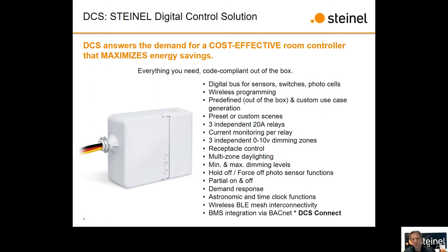One of the strongest differentiators in the DCS is the 3 independent 20 amp relays, where all the other guys in the market give you one 20 amp relay divided across 3 channels. Why is this so important? Well, our DCS can allow you to have both 277 volt and 120 volt circuits on the same controller. So if your plug load is running at 120, but you've got 277 specialty lighting in the same space, and maybe some 120 volt regular lighting too, I can split those onto 3 different circuits, switch legs, using the 3 different relays. Additionally, it gives you a lot more power to manage an entire circuit, since each relay is 20 amp rated.